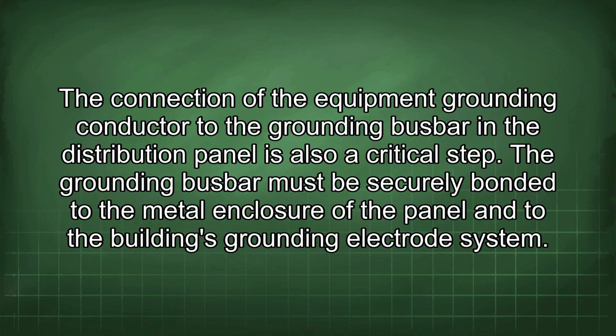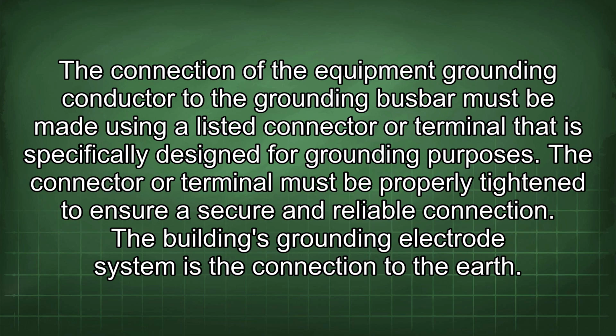The connection of the equipment grounding conductor to the grounding busbar in the distribution panel is also a critical step. The grounding busbar must be securely bonded to the metal enclosure of the panel and to the building's grounding electrode system. The connection of the equipment grounding conductor to the grounding busbar must be made using a listed connector or terminal that is specifically designed for grounding purposes. The connector or terminal must be properly tightened to ensure a secure and reliable connection.